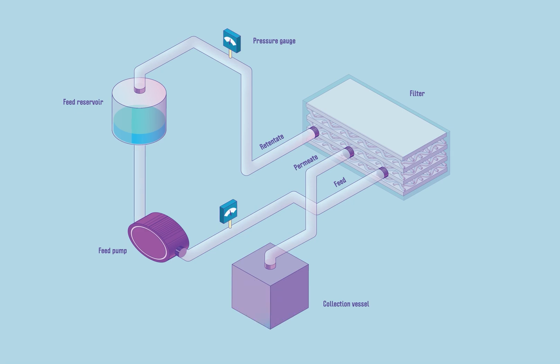The material is fed in from the feed reservoir by a pump and enters the filter via the feed line. Material that does not pass through the membrane is called the retentate and is usually pumped back into the feed reservoir. Material that transits the membrane is called the permeate and can be collected separately in the collection vessel.